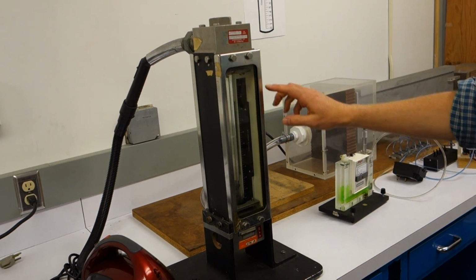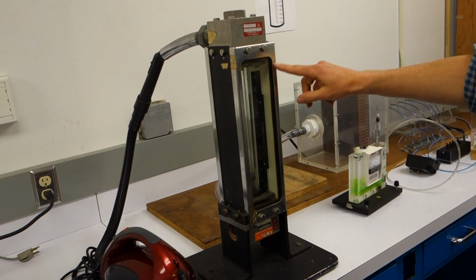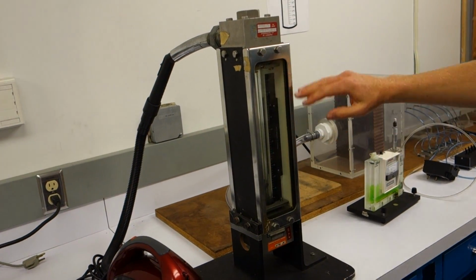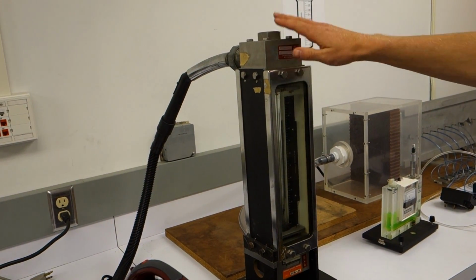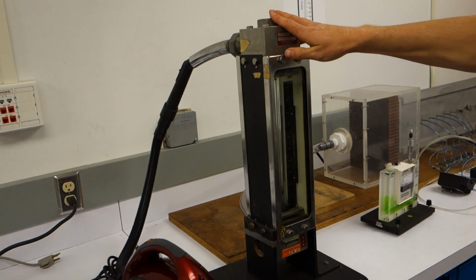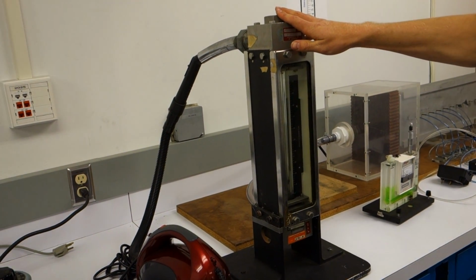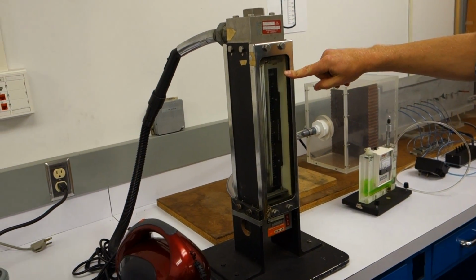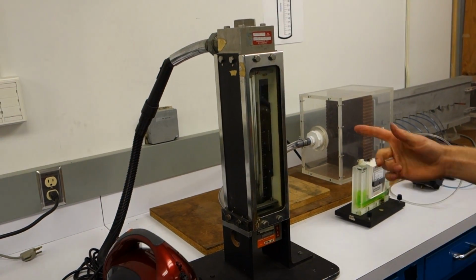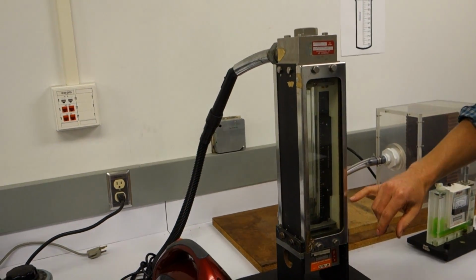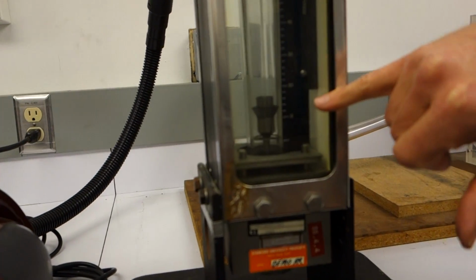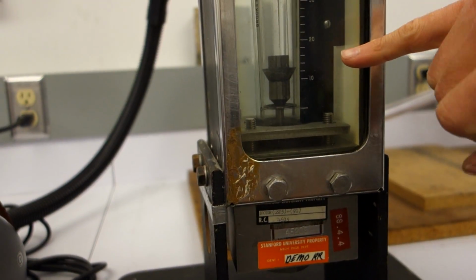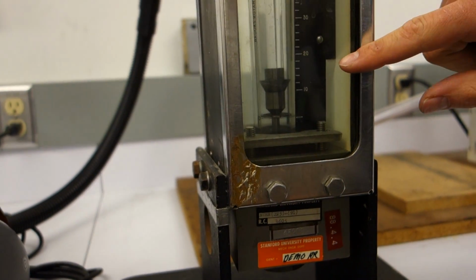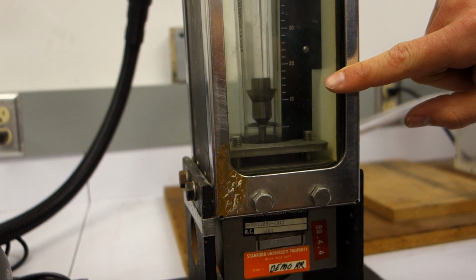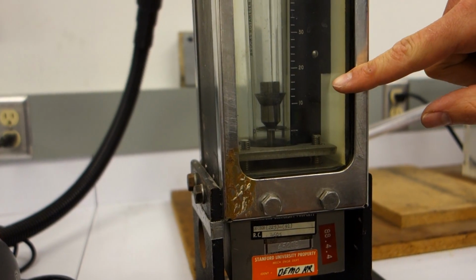So the numbers here read from 0 to 100, which is a percentage of maximum flow. This device here is calibrated for 34.6 cubic feet per minute at 100% maximum flow. And we read the level of the flow right at the top of the taper of that bobbin. So right where it opens up like this, we're going to read it at that top. Right now it's reading 12% or so, but it's actually at zero.